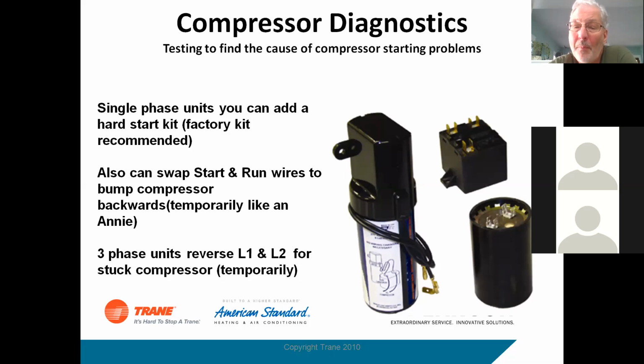And you can also try to bump them backwards. Sometimes you can take the run and the start wires, reverse them, and just give that compressor a quick bump. And that's basically, if anybody's ever seen an analyzer, a compressor analyzer, that's basically what you would do. You just give it a quick bump backwards to see if you could break it free. If you do that and you try a hard start kit and you still can't break the compressor free, it's stuck. It's going to have to be replaced at that point. But there are some components available on the single phase units that we can add to try to do that.